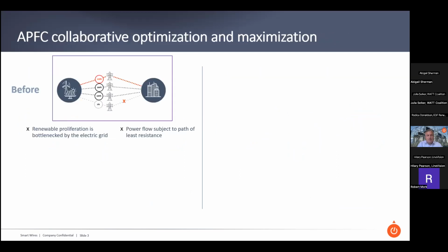Let's talk about the interaction with other GETS technology. So we go back to our original position - we've got the before situation, we've got an overload on one of the lines. In this case the network's a bit more loaded, so what we see is 120% on the line that's overloaded, but both adjacent lines are at 100%.